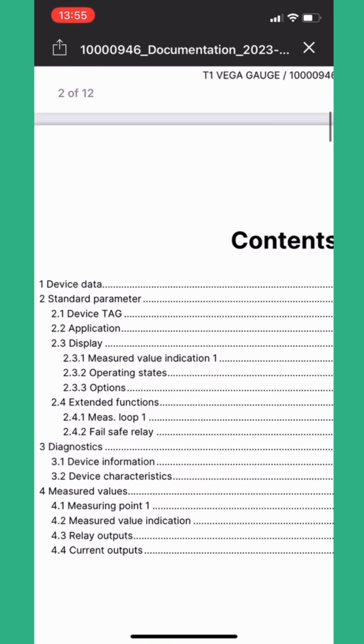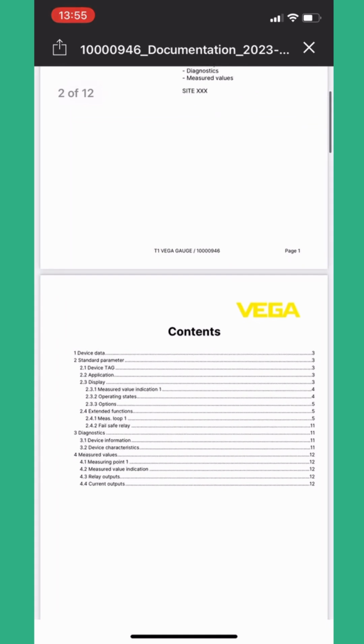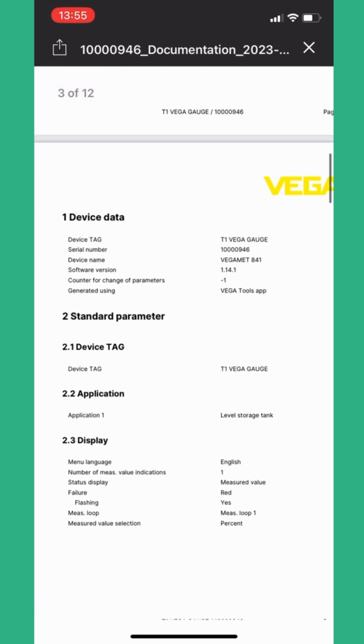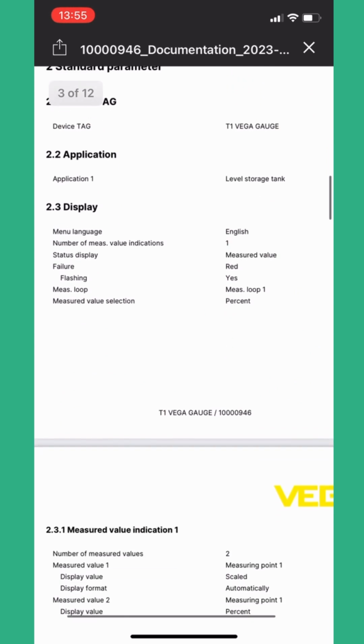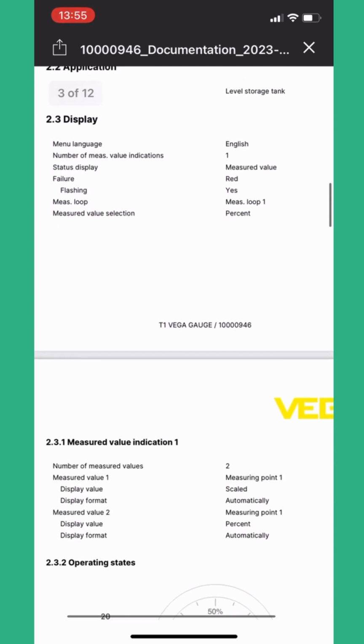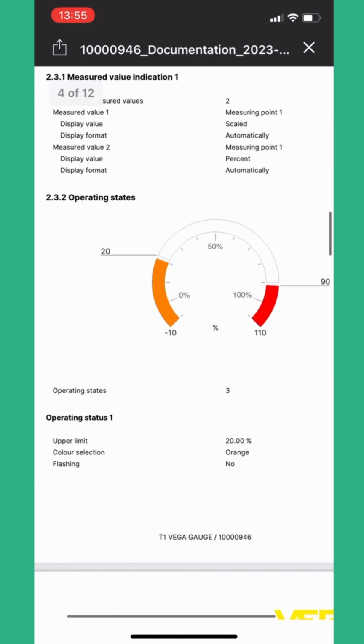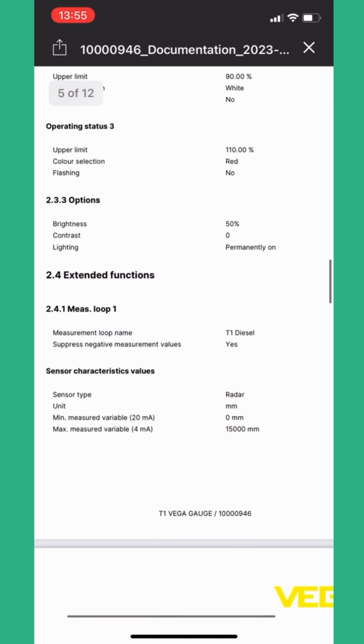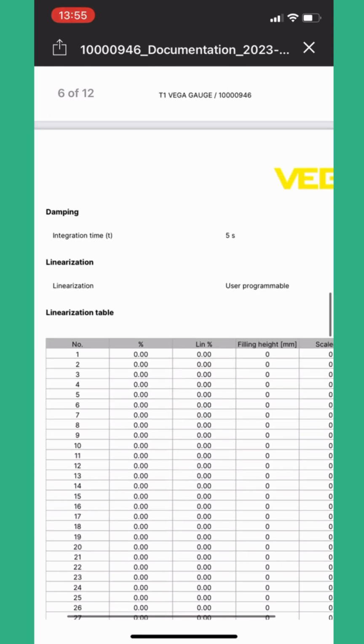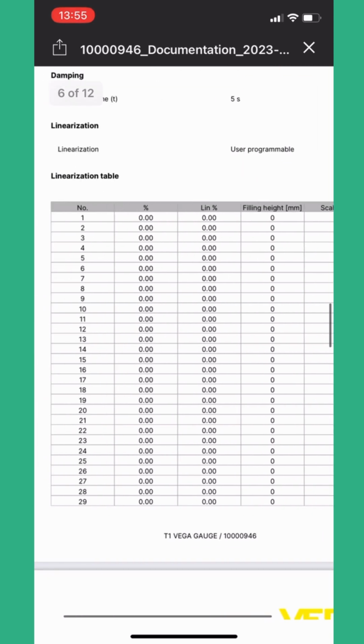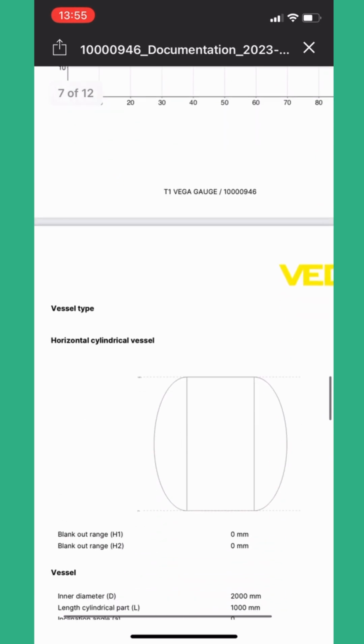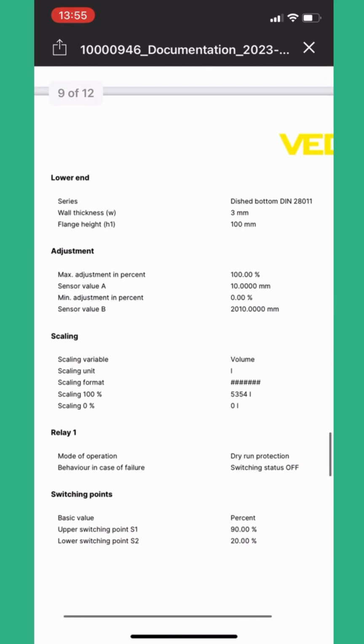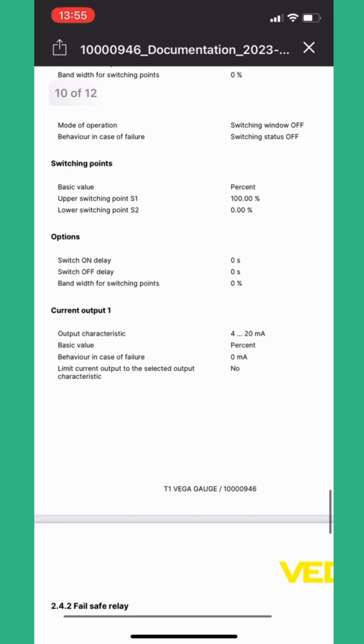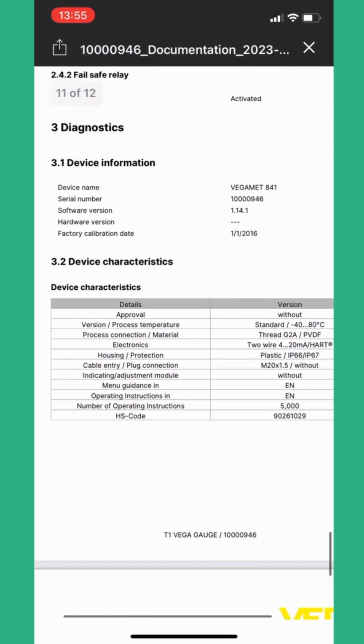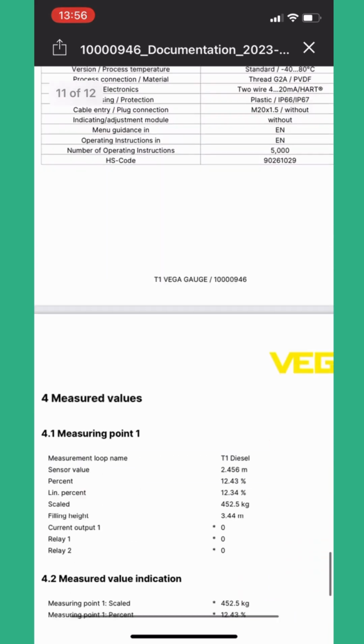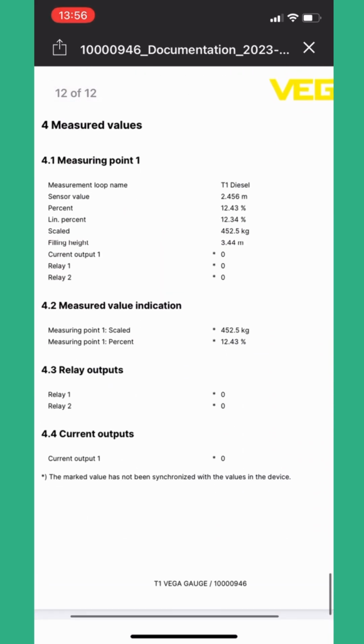You can see on here that it gives you a menu of everything that's going to be contained within the PDF, and then it tells you the device data, the tag, how the display was set up, what measured values we're taking in, how the display colors will change based on operating states, and we can see the scaling that we've inputted. We can see the linearization, the tank calibration chart that's been inputted. We can see a linearization curve. We can see what type of vessel and any other adjustments, and how the relays will activate, as well as diagnostics of the device at the time that this document was printed.